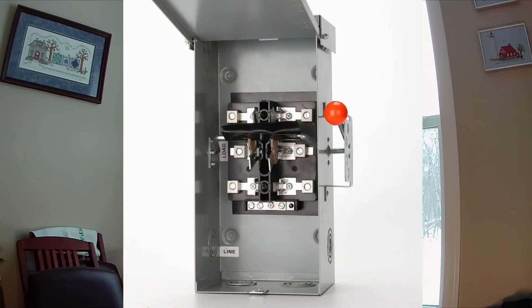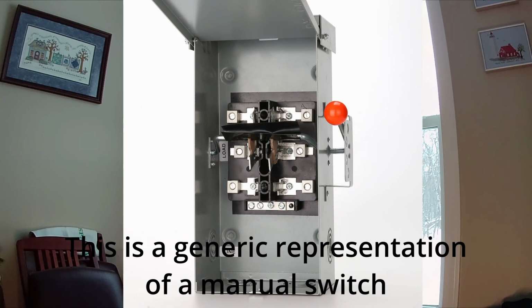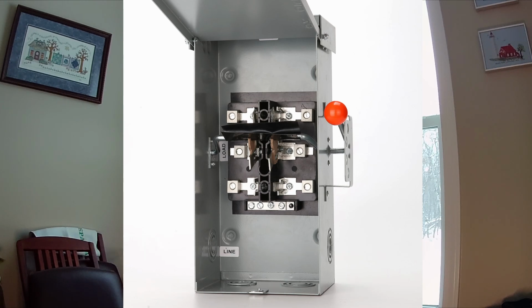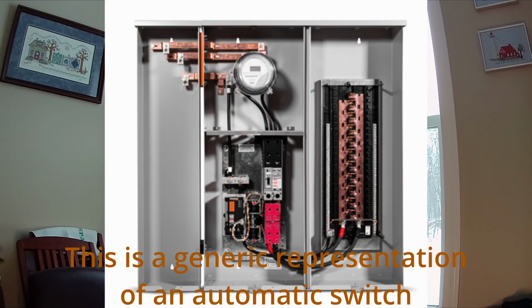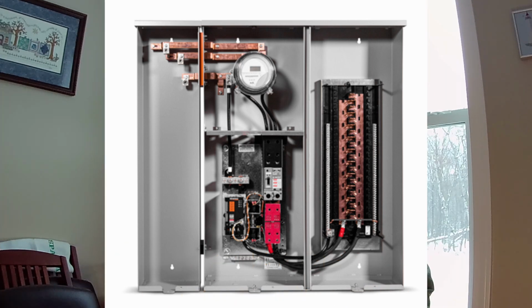Transfer switches come in two basic flavors. You have a manual transfer switch and an automatic transfer switch. Just like the name suggests, the manual transfer switch requires that you switch from grid to generator manually. The automatic transfer switch monitors the grid, and when the power goes out or even starts to fluctuate, the transfer will call for the generator to start and then take over for the grid and power the house off the generator. This will continue until reliable power is restored.